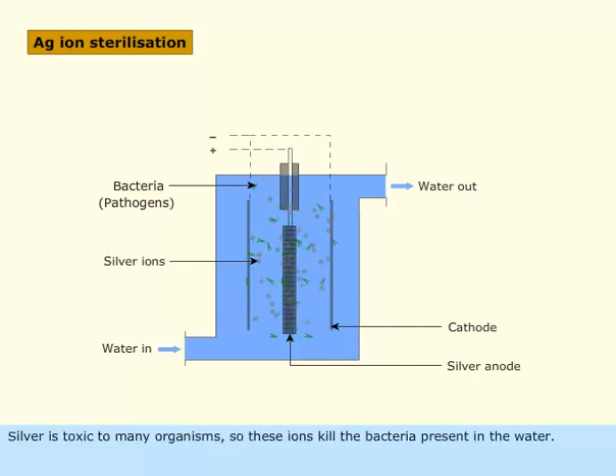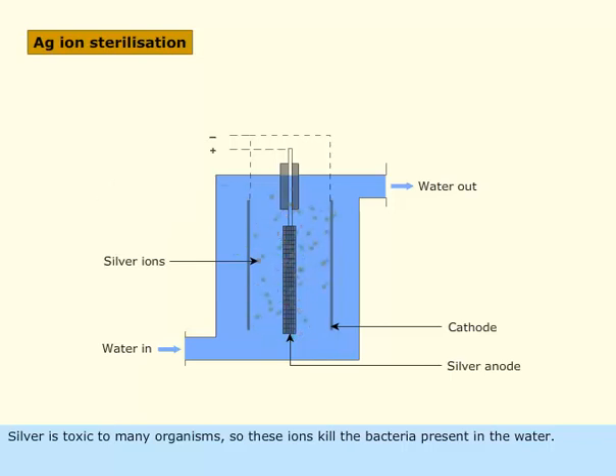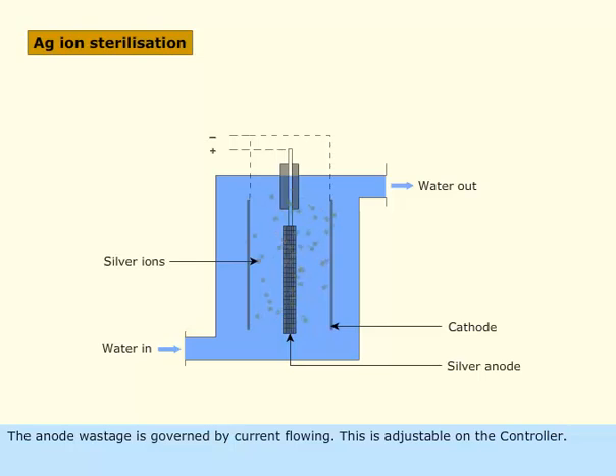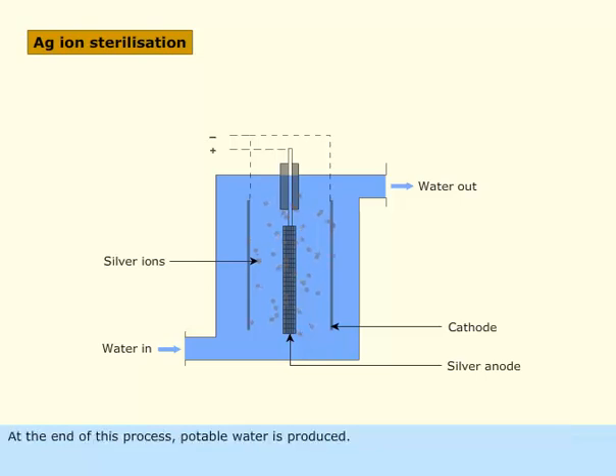Silver is toxic to many organisms, so these ions kill the bacteria present in the water. The anode wastage is governed by current flowing, which is adjustable on the controller. At the end of this process, potable water is produced.